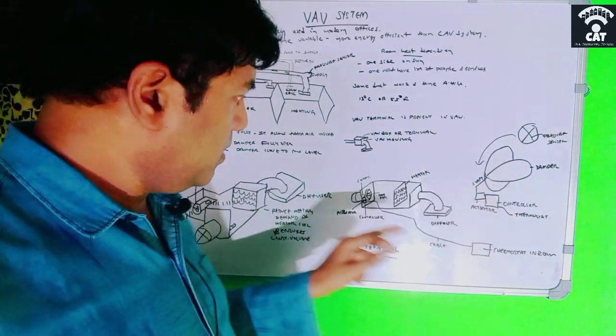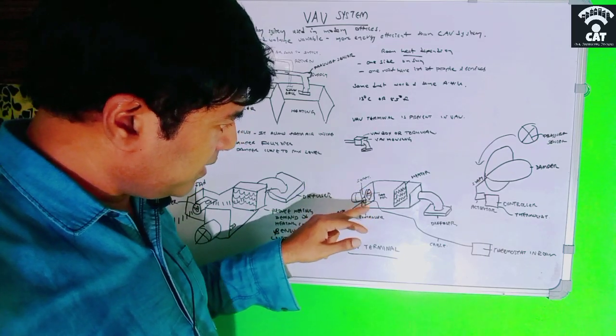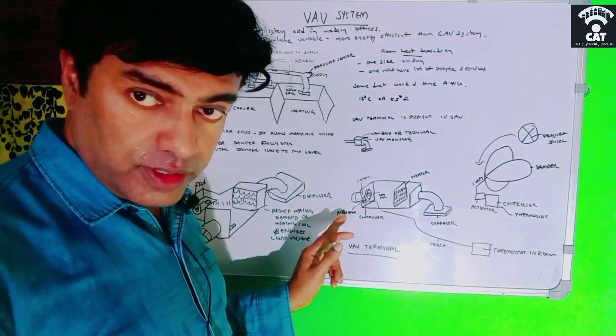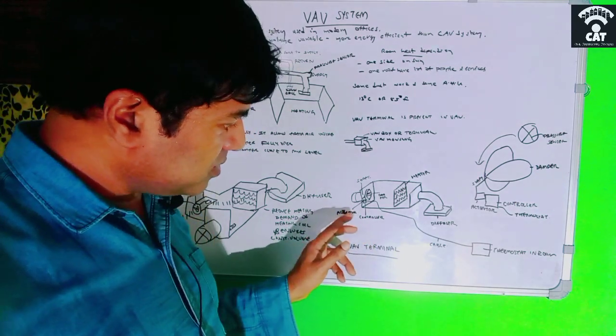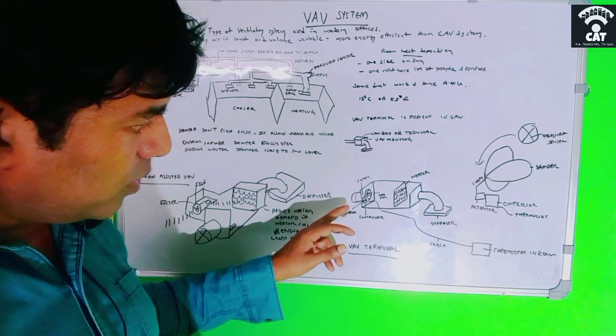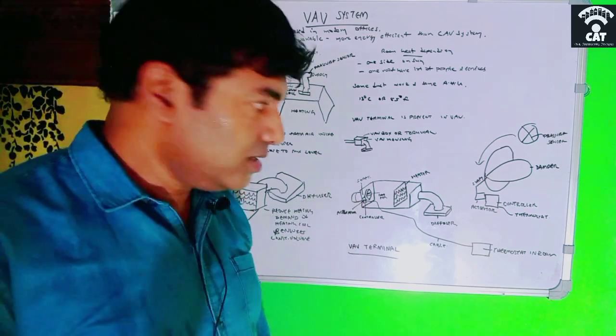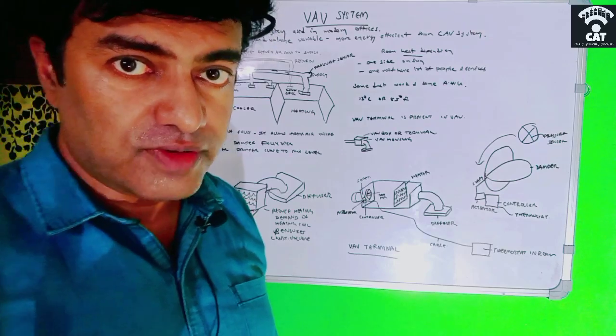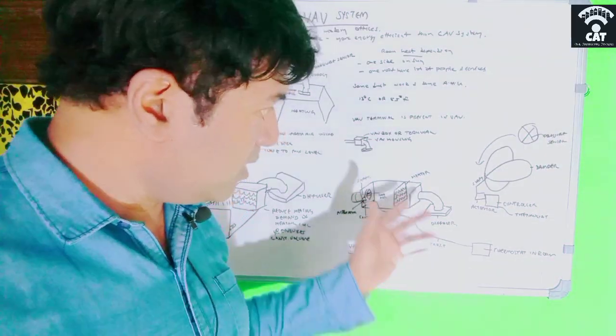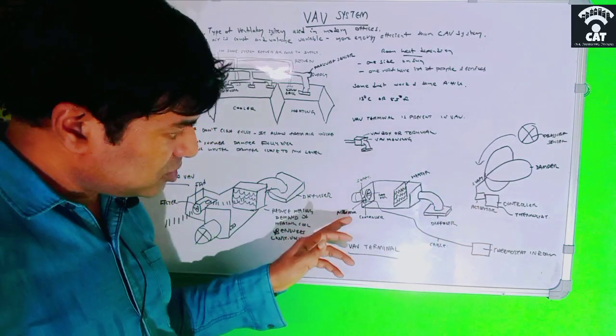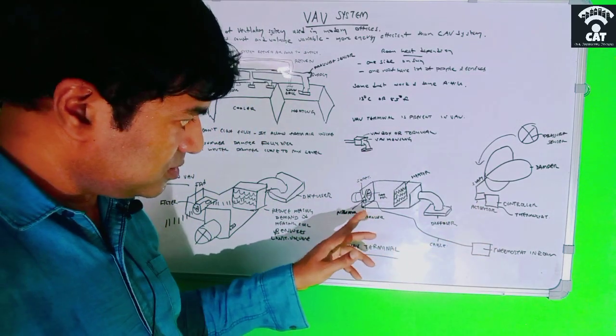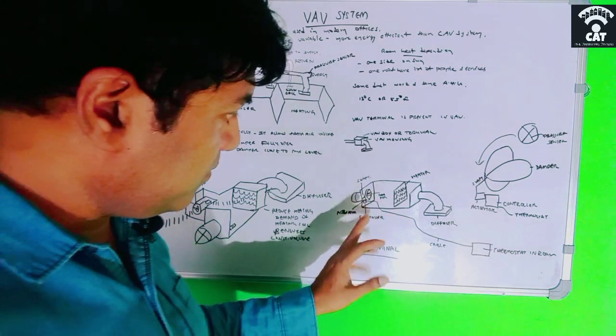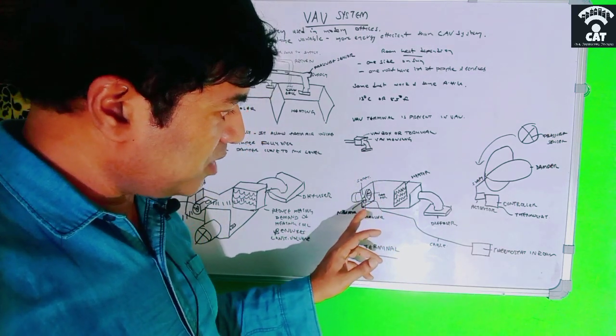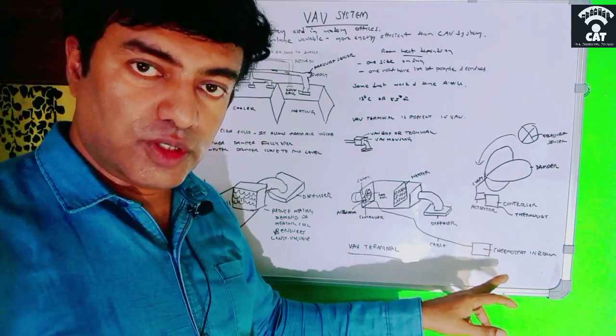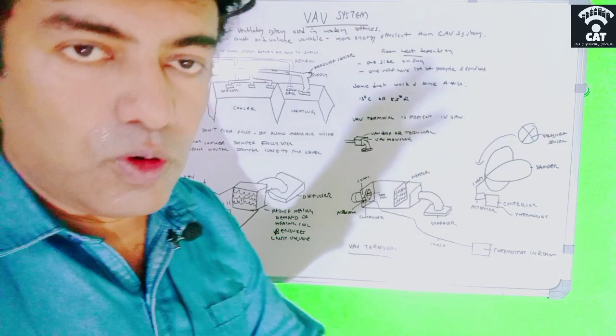This damper, this circular thing, is connected to an actuator, and the actuator is connected to a controller. The actuator has a shaft. In the actuator there is a small motor which can rotate the shaft, and when the shaft gets rotated, this damper will also get rotated. The connection for the actuator is in the controller. There is another small piece of equipment called the controller, and this controller is connected to the thermostat, which is situated inside the room. You may have seen the thermostat in all the rooms, through which we can control the temperature in that particular room.